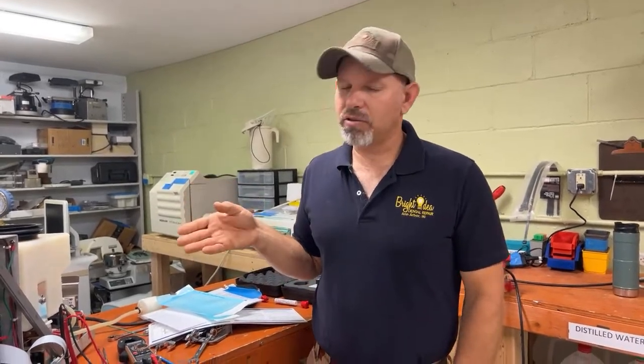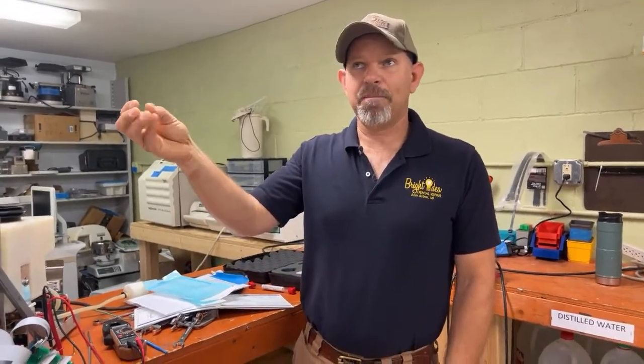And I know there's a lot of times where there's a problem, and the first thing people want to do is, hey, change out the main board, because that affects everything. That's just not always what it could be. It could be the main board, obviously, but it could also be the wiring. There could be a problem with the component itself. There could be some sort of a loose connection. There could be all kinds of different things. Here, there could be an issue with the calibration, how the things are calibrated.